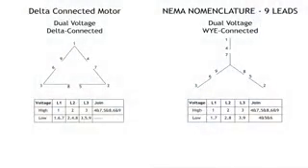If we're missing a number on one of our leads, by looking at the actual configuration and checking for continuity, we can pretty much have a good idea which number is missing. If we have, say, 1 and 4 has continuity and you've got a 1, you're missing number 4, then we know that the one that has continuity with number 1 is number 4. If you're missing number 1 and 4, or the 2 in the same phase, then we've got to do this completely different.